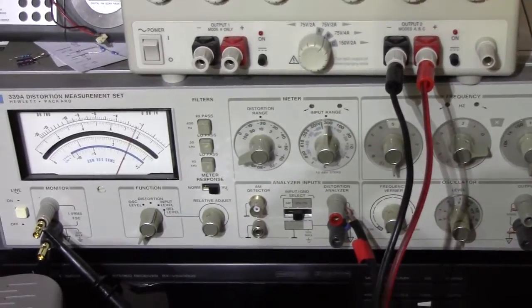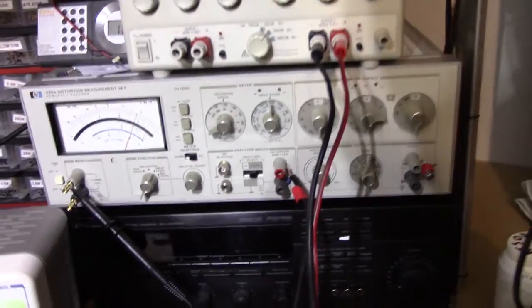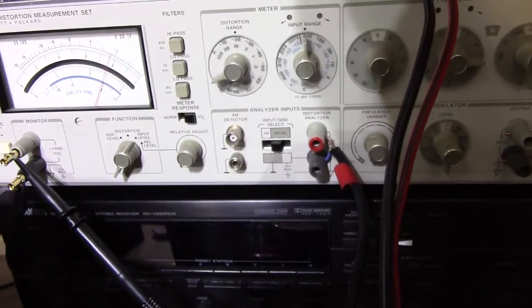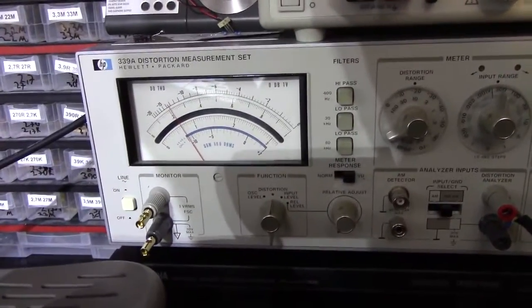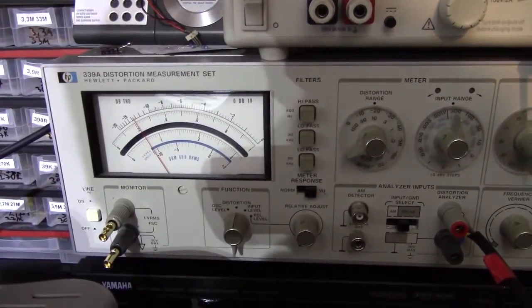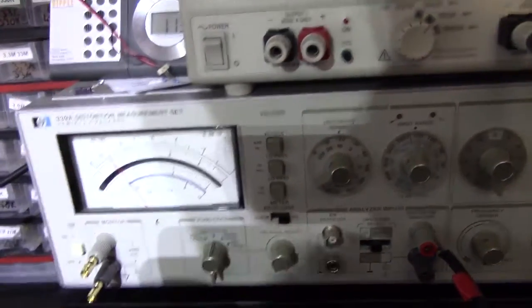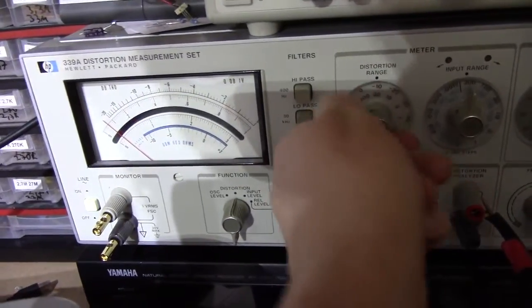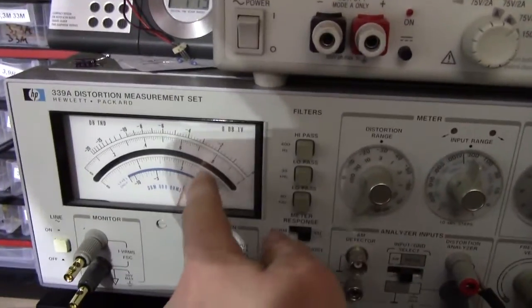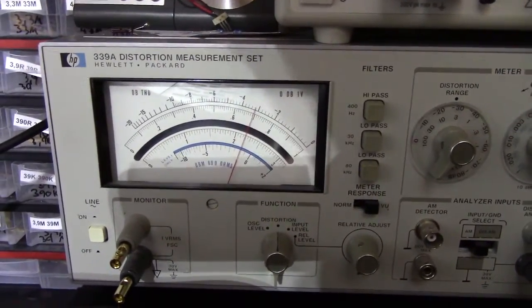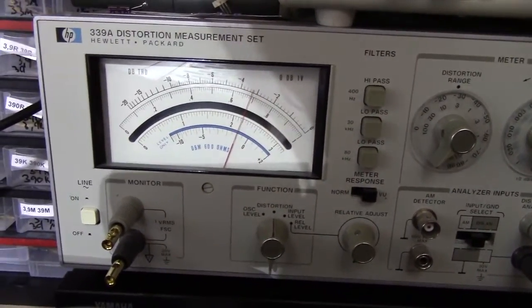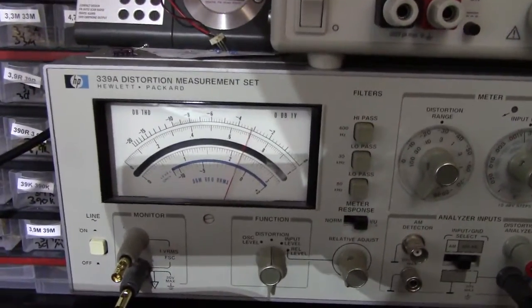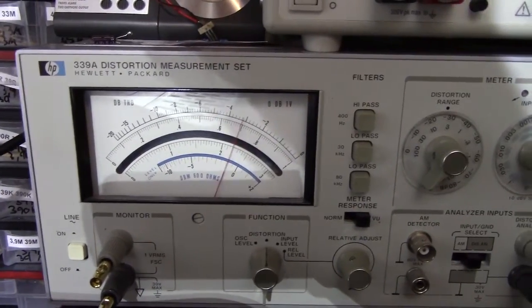Now, I am somewhat hesitant to disconnect the ground with a cheater switch on this thing when I'm measuring high voltages like mains. The grounding of the output buffer amplifier or the monitor buffer amplifier is definitely what's setting up our measurements here. Because we're now measuring distortion at 10% full scale. And, well, that's a bit hot actually. 3% full scale and we've got about 2%, just over 2% distortion on the waveform of this UPS under load. And that's even with no low or high pass filtering. So yeah. This UPS is performing very, very well. 2% distortion under about 50% load is more than you can ask for.